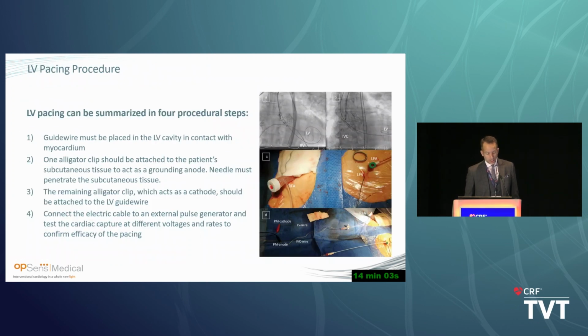So the actual pacing part of the procedure is not too difficult. I do think it's a little bit easier than the way we've been doing it off-label, where you have to scrape the wire and make a little incision and put the electrodes in the skin of the patient. For this one, you make sure that your guide wire is placed in the LV cavity in contact with the myocardium. When we're using Safari wires or whatever your favorite wire is, you have to make sure you really bury the wire. That's less important here because you're pacing at any point along that curl. As long as it's in the LV and you can tell there is some contact with the myocardium, you don't have to really push it in, which matters because some of these patients have quite frail tissue, and you don't want to be pushing things too much if you don't have to.